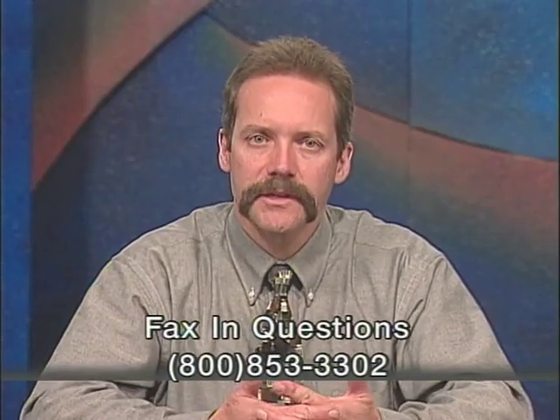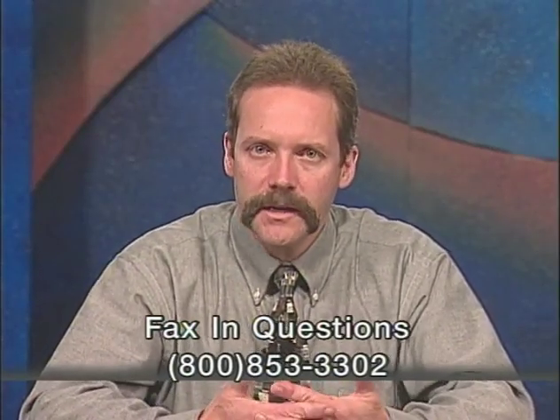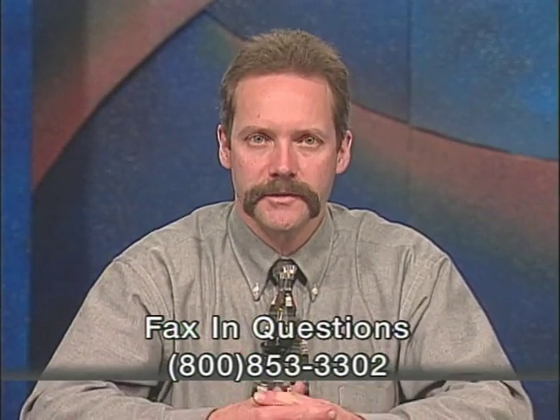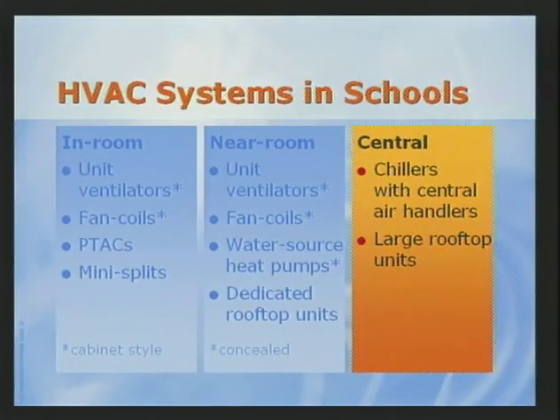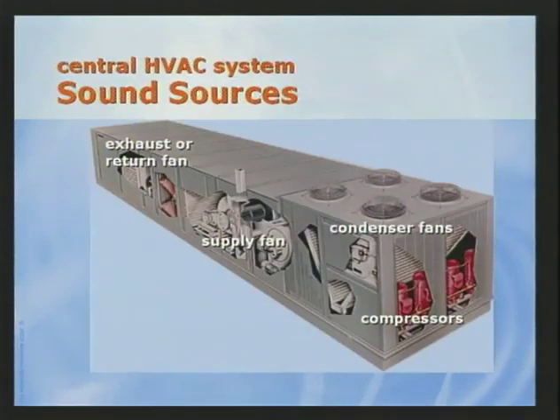Okay. Central systems generally have the loudest sound sources because for a single unit to serve many spaces, it must have more airflow, and more airflow generally means more noise. However, central systems can also offer the greatest flexibility in path attenuation. Units in this category include chillers with central station air handling units and large rooftop air conditioners. A good example of the concentration of sound in the central system is a large rooftop unit. A single enclosure houses a supply fan, a return or exhaust fan, plus the refrigeration compressors and condenser fans, all of which generate sound.